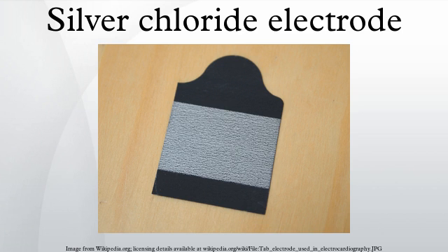Silver chloride electrodes are also used in many applications of biological electrode systems, such as biomonitoring sensors as part of electrocardiography and electroencephalography, and in transcutaneous electrical nerve stimulation to deliver current. Historically, the electrodes were fabricated from solid materials such as silver, brass coated with silver, tin and nickel. In today's applications, most biomonitoring electrodes are silver-silver chloride sensors, fabricated by coating a thin layer of silver on plastic substrates, with the outer layer of silver converted to silver chloride.